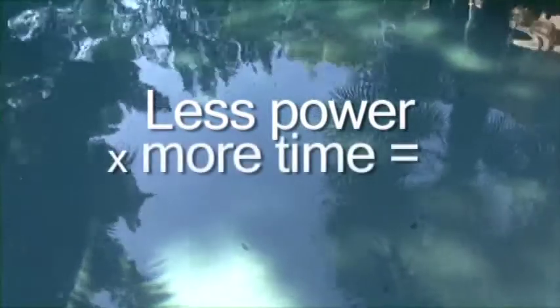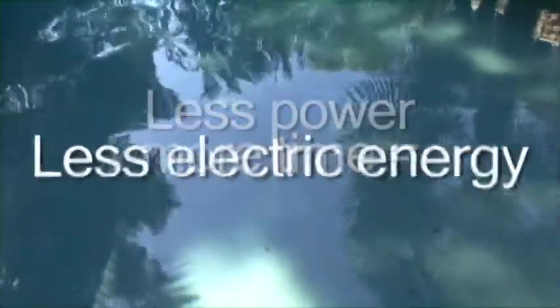So instead of going 6 hours a day, we might run it 12 hours a day, but at dramatically less cost. And in giving you that 75% savings, I've taken into account the fact that you need to run the pump for a longer time. So it's counterintuitive. Most people would think longer time, more electric energy. Not so. Less power times more time results in less electric energy use.